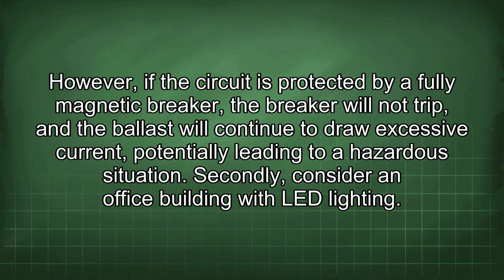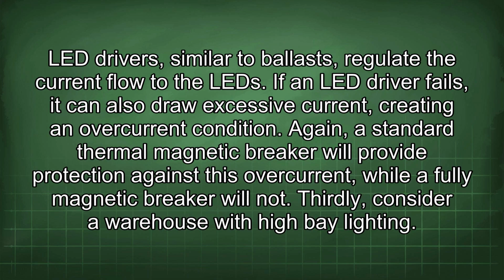Secondly, consider an office building with LED lighting. LED drivers, similar to ballasts, regulate the current flow to the LED. If an LED driver fails, it can also draw excessive current, creating an overcurrent condition. Again, a standard thermal magnetic breaker will provide protection against this overcurrent, while a fully magnetic breaker will not.